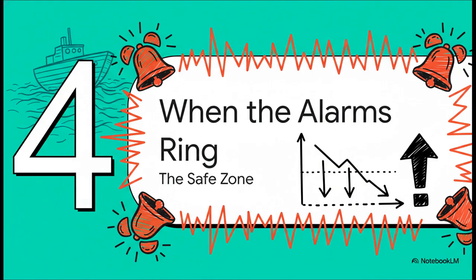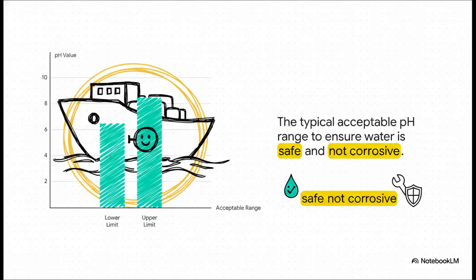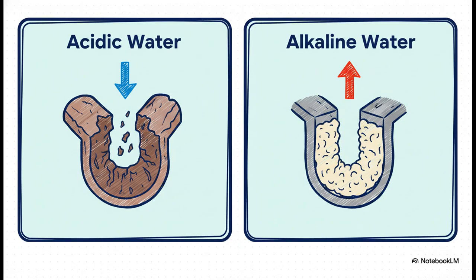Well, this is where the system really proves its worth, by sounding the alarm before a small problem can turn into a major disaster. See, for water produced on a ship, there's a kind of Goldilocks zone. Typically, the pH needs to stay somewhere between 6.5 and 8.5. That range makes sure the water is safe to drink, but also won't damage any of the ship's expensive equipment. And here is exactly why that zone is so important. If the pH drops too low, the water gets acidic and will literally start to eat away at pipes, tanks, and machinery. But if it goes too high, it becomes alkaline, and you get mineral scale building up, clogging systems, and messing with sensors. Neither one is a situation you want.